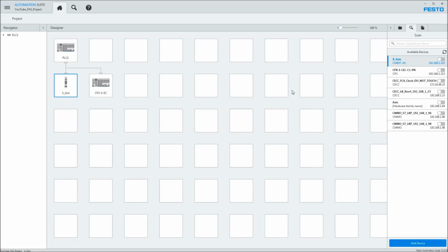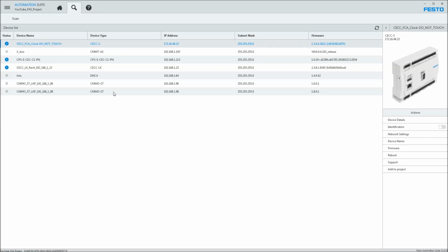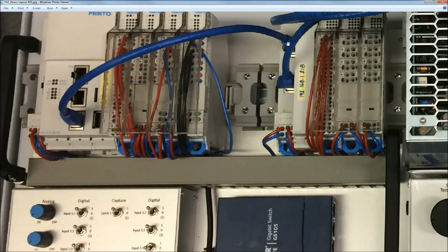scan that's in Automation Suite here, this tool right here, and the same as this. In order to see it in there, this tool here uses UDP commands, and the UDP commands are not supported through the backplane of this PLC here on the EOE. So the trick here is to disconnect the EtherCAT ports and connect directly from your PC.